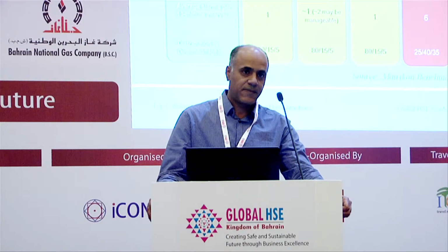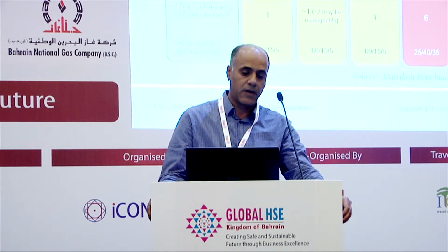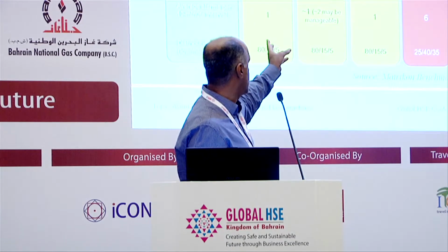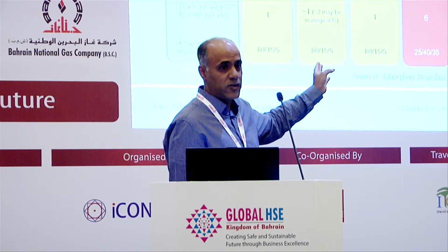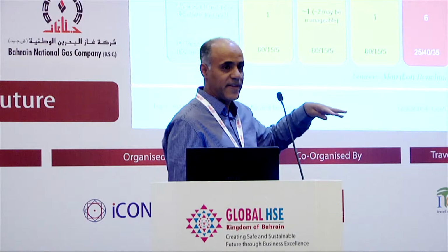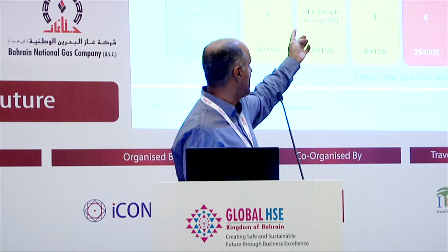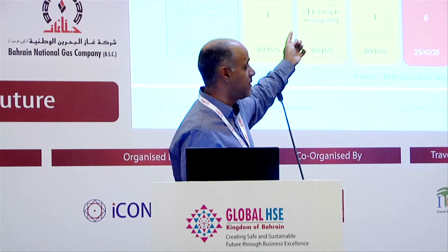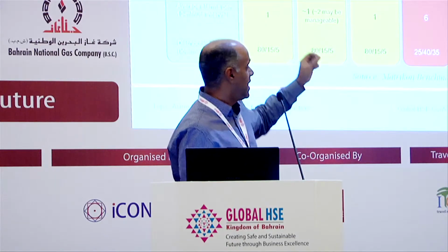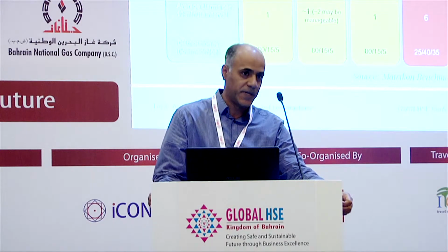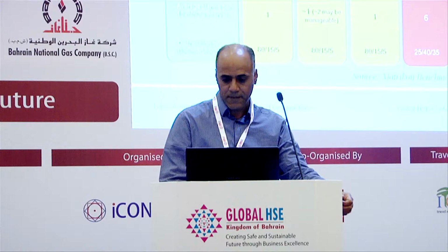The standards and research done by different organizations like EEMUA, ISA, or ASM suggest that the yellow part of the chart is the best practice for the rate of alarms that any operator can handle. But the reality is the red columns, where you can see that, for example, in oil and gas, the number of alarms appearing on a 24-hour basis is 1,200 alarms per day, which is an average of 1 alarm per minute.